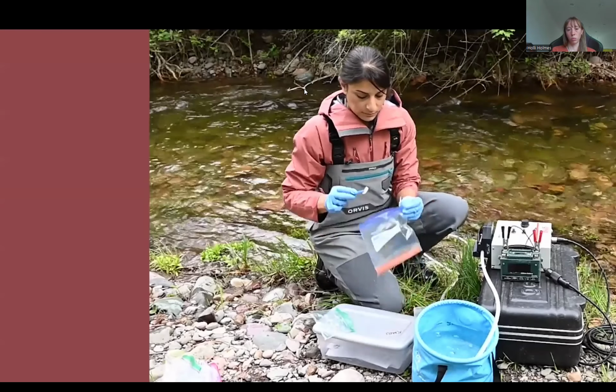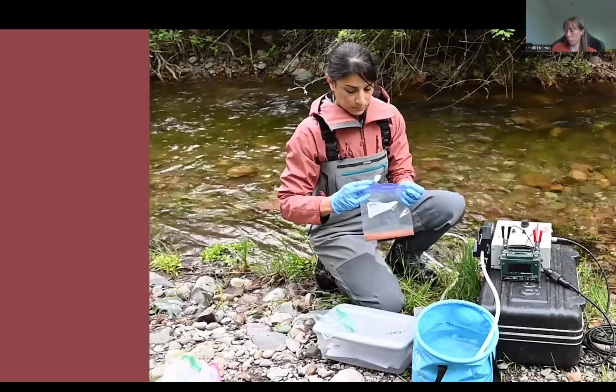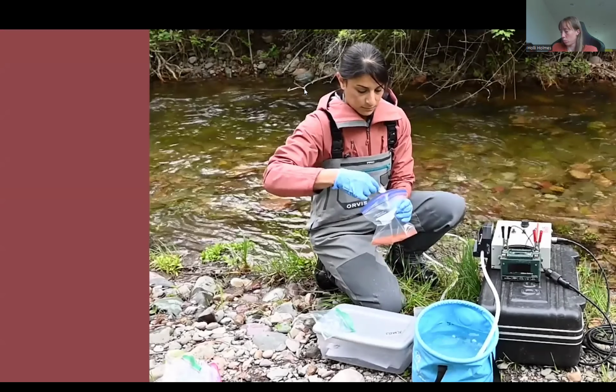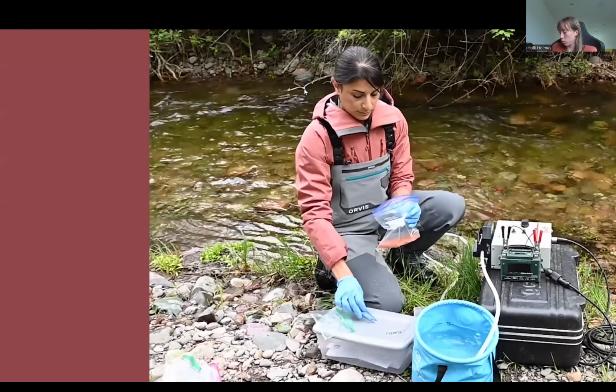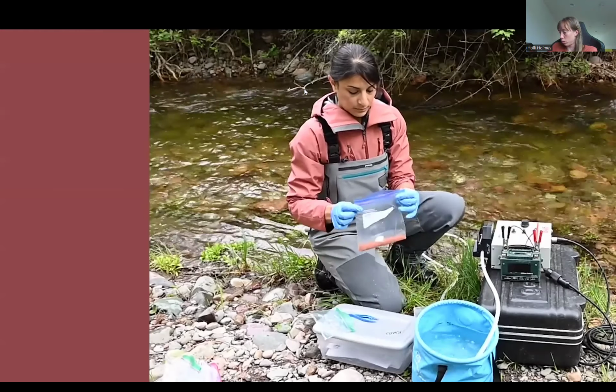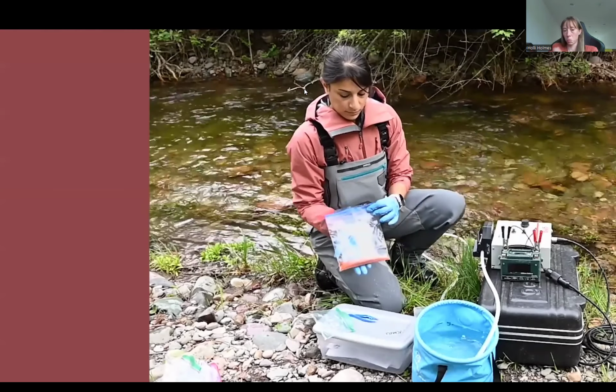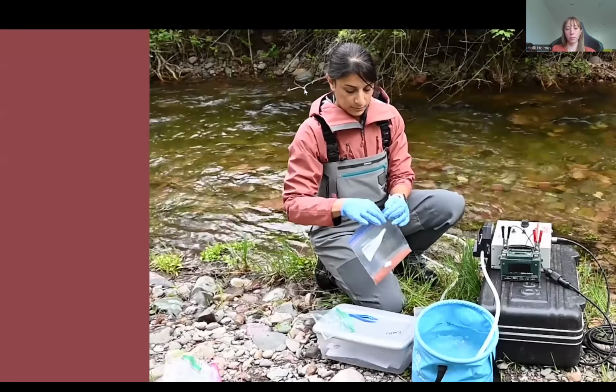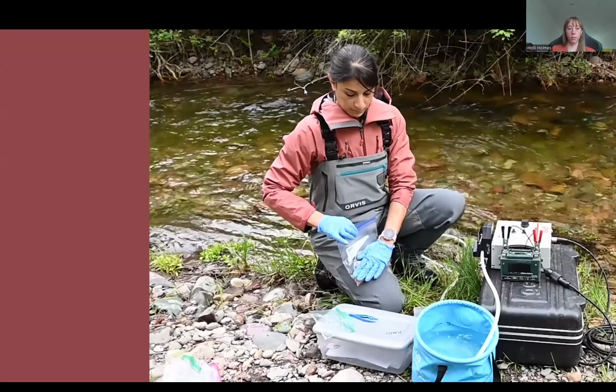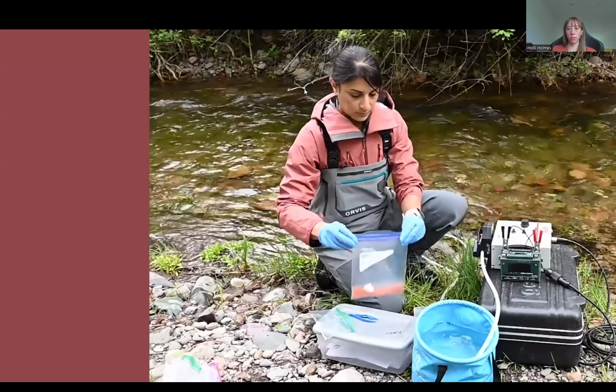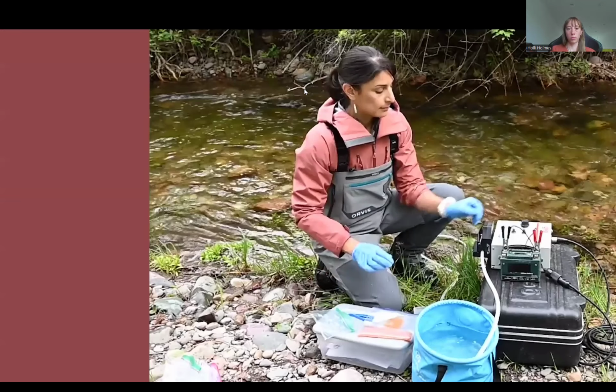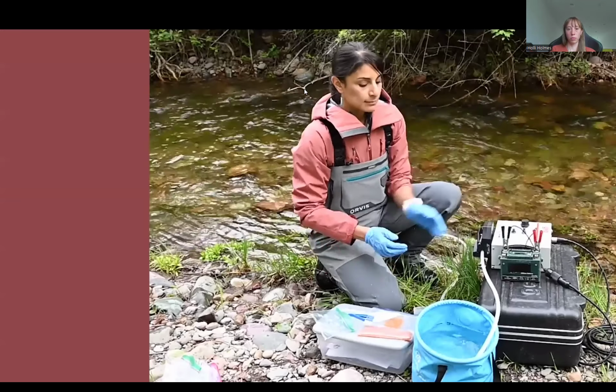Add the filter to the bag with silica desiccant. Minimize the risk of contamination. Drop the filter into the bag, taking care not to insert your hands into the bag. Make sure the filter makes contact with the desiccant. Expel the air from the bag and seal it. You may now turn off the pump.